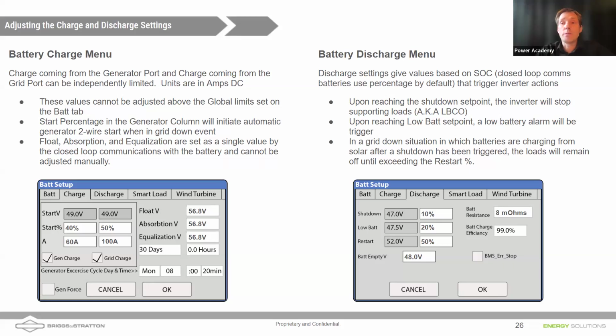No, that's a great idea. Really, that's best practice, Daniel. So what we want to do is make sure that battery is safe in the event of a loss of comms. And the best practice there really would be to come in, program the float at 54, the absorb at 56, the equalization at 56, and then the 0 hours on the screen before you set up the comms. That way, if we do ever lose communications, those safer values are going to be in there.